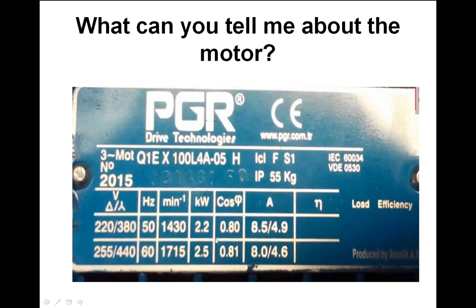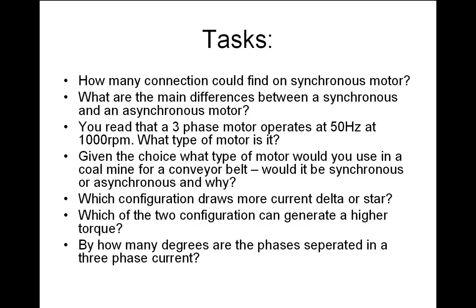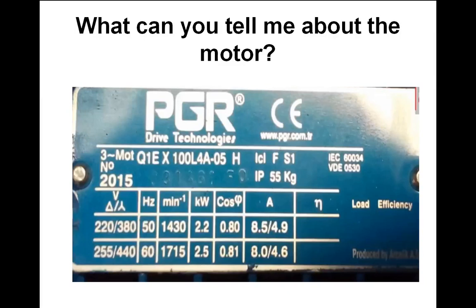We've got another motor plate. Hayden and Ryan identified it as three-phase. To work out pole pairs, look at the RPM. If it was 60 Hz, synchronous speed would be 3600. The RPM shown was 1715, which is roughly half — so two pole pairs. If it were three pole pairs, it would be below 1200 RPM.